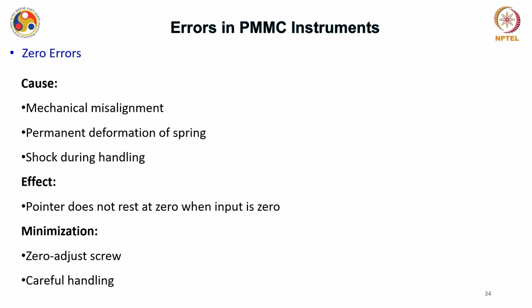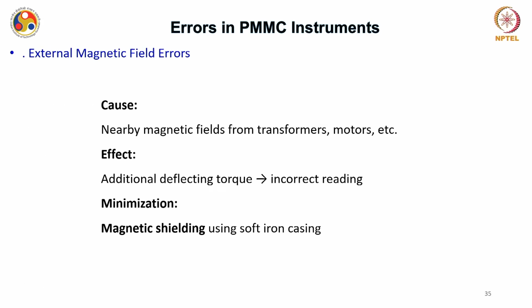Okay. This is mostly because of mechanical misalignment, but permanent deformation of the spring or shock during handling of the tools are some of the other causes behind this zero error. Okay. And the effect is that the pointer will not rest at 0 when the input is 0. So, it will show a certain value which is not the actual value. There is no input, but you still have some output which is not desirable. Okay. So, this can be minimized by adjusting the screw known as the zero adjust screw. Okay. Then by careful handling, where you take care of the instrument and do not allow any external shock during handling. Okay. So, these are certain ways by which you can at least minimize this zero error.